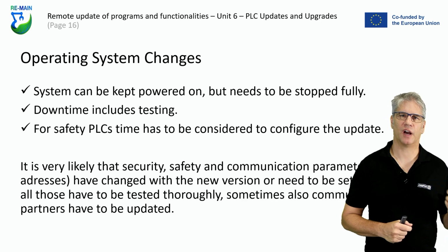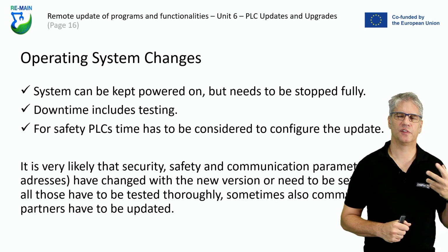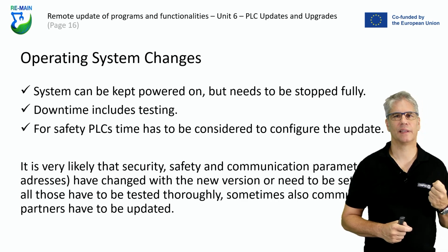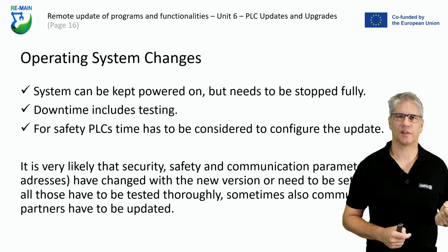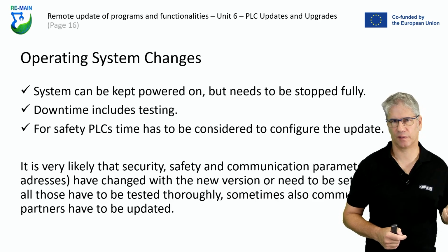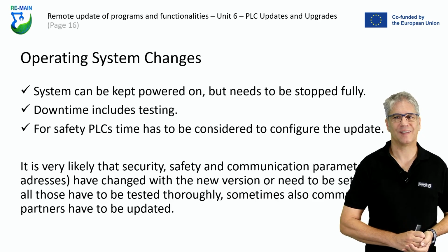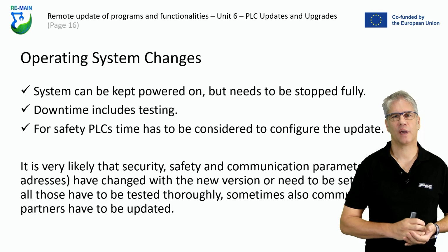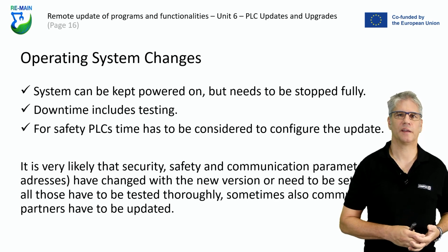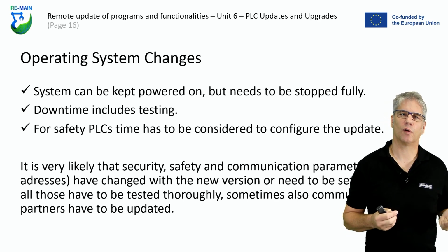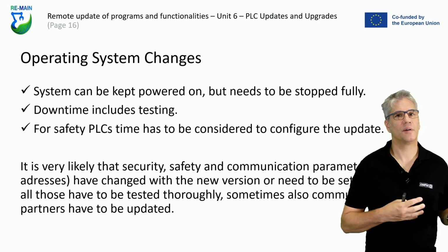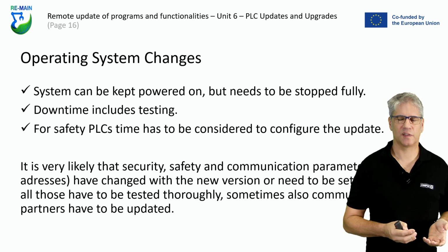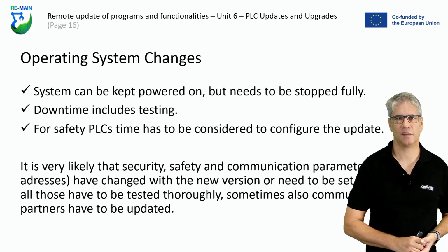Because you do not change the hardware, you change the system on the hardware, which means that you have to do some installation, and this installation normally takes some time. And after you power up and start up the system again, you will have to test the functionality. And if you have safety PLCs, which is quite likely nowadays, so that the PLC also includes all the safety mechanisms, then you have to consider that also updating this, or at least reconnecting this, will also take some time.